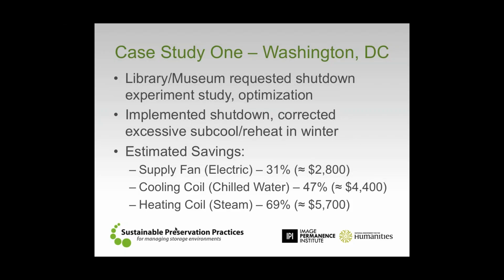And we found a couple of things. We did go in and implement the shutdown that they wanted to test out and experiment with, and we tried that and pulled the data and figured out that, all right, for some of their spaces, they could run an 8-hour shutdown without dangerous fluctuation. And for other spaces, particularly in the wintertime, we found out that they could run upwards of a 10 to 12-hour shutdown at night without seeing any significant fluctuation in temperature in the space at all. And by the way, in these cases, most of the time, if RH fluctuates at all, it's as a function of the temperature. So 1 or 2 degree fluctuation in temperature is not much movement in relative humidity at all.